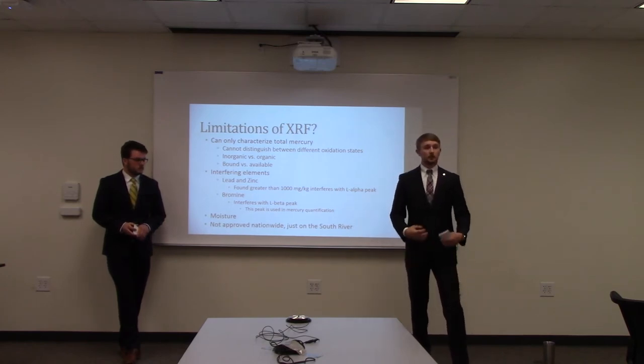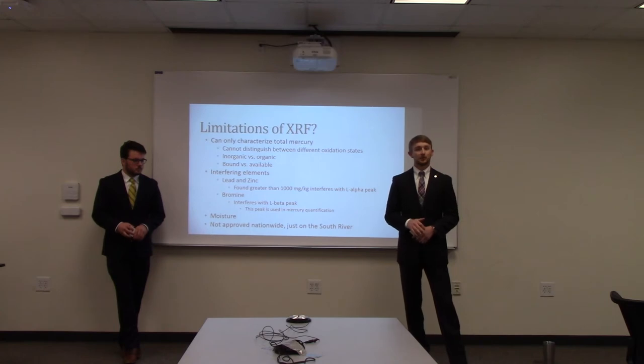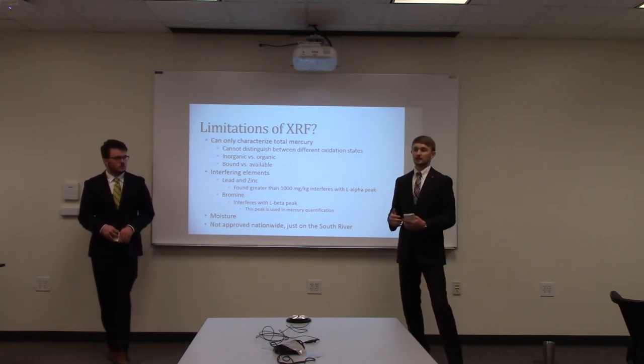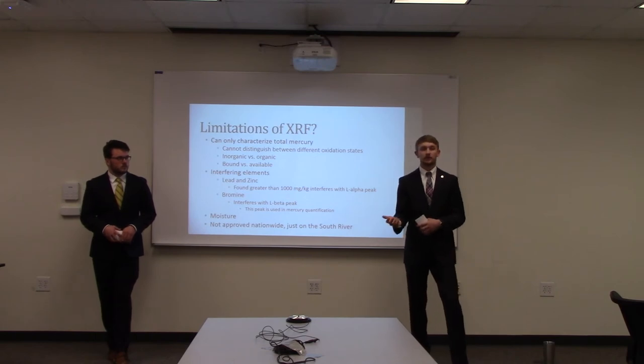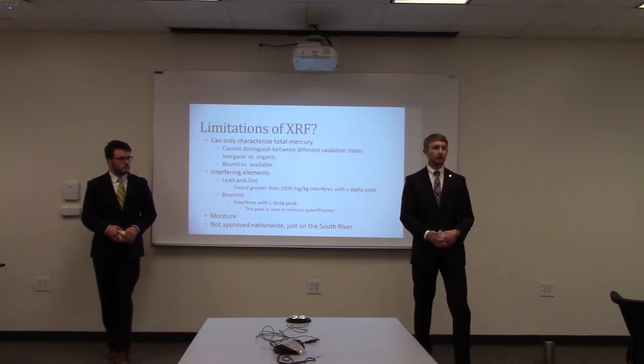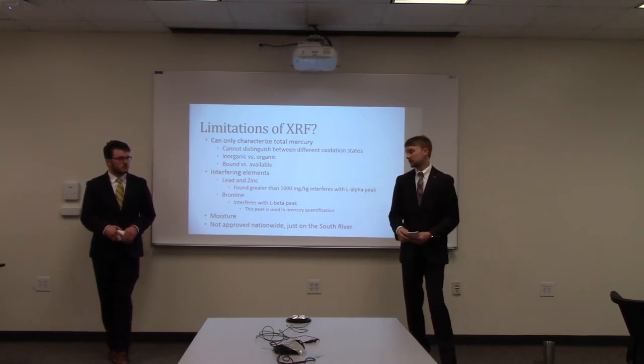We used a moist sample calibration, so moisture wasn't a limitation as much as it could have been. But if the site-specific calibration isn't used with this device for the site you're using it on, moisture could be a limitation of the device.